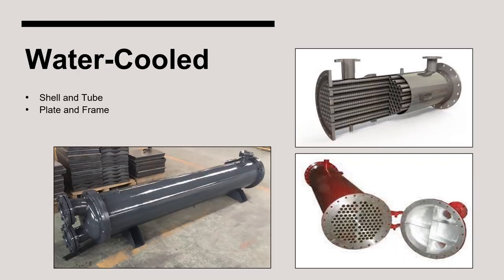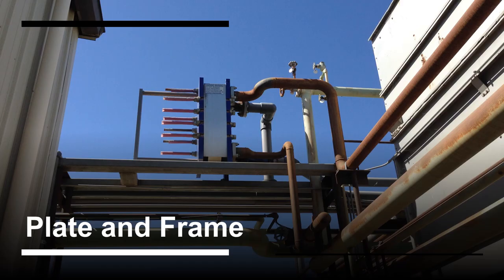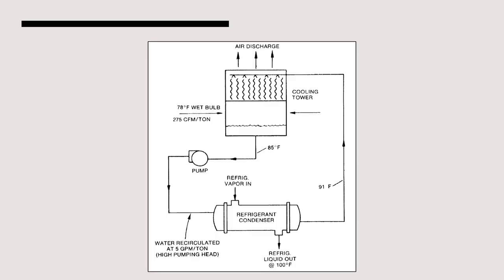A water-cooled condenser does not rely on air for cooling but only relies on water. These condensers come in the form of either a shell and tube or plate and frame type heat exchanger. Here is an example of a plate and frame heat exchanger which serves as a water-cooled condenser. An additional aspect of water-cooled condensers is the associated cooling tower. Once the water in the condenser absorbs heat from the ammonia, the warm water will need to be cooled down before it is reused. This is accomplished through a cooling tower.